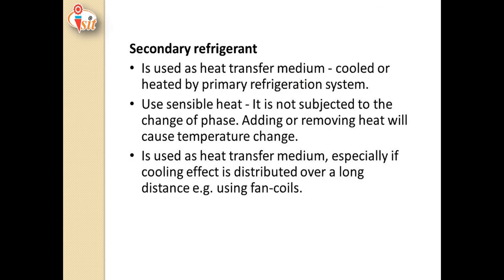Secondary refrigerants are used as a heat transfer medium only — cooled or heated by the primary refrigeration system using sensible heat. Latent heat is not used; only sensible heat is absorbed by the secondary refrigerant, so there is no change of phase. These secondary refrigerants are used especially when the cooling effect is distributed over a long distance, for example using fan coils.